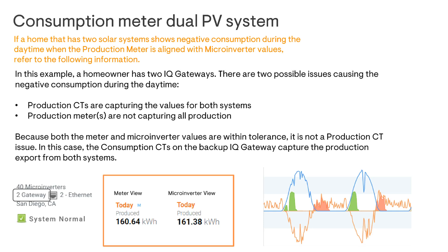Take a look at this example. Microinverters measure production values at a 95% accuracy rate, while production CTs measure production at a 99% accuracy rate. When comparing the two, the difference should not exceed 4.5%. Here you can see the meter and microinverter values are within this range, so this is not a production CT issue.